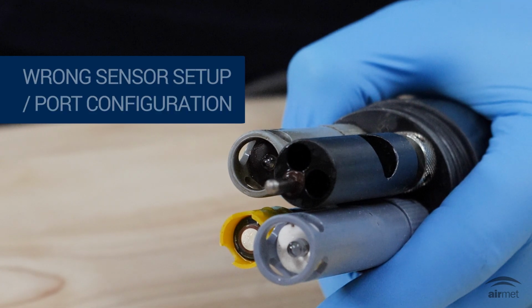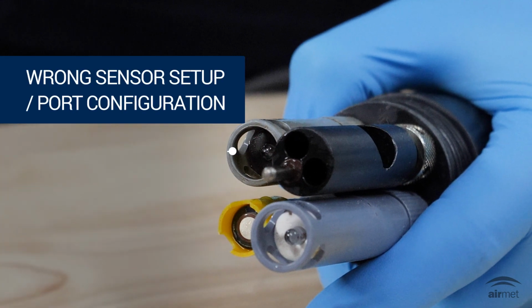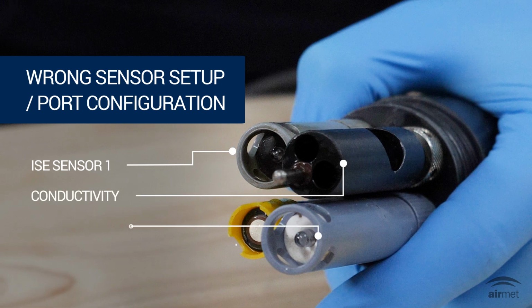Wrong sensor, setup port, and configuration. On 4-port Quattro cables, port 2 has no reference of its own. It uses the reference from the pH or ORP sensor in sensor port 1. You must have a working pH or ORP sensor in sensor port 1 for any second pH or ORP results in sensor 2 to work properly.